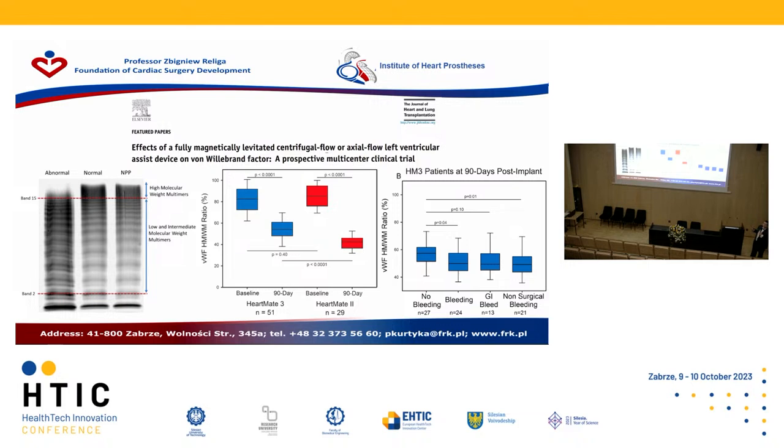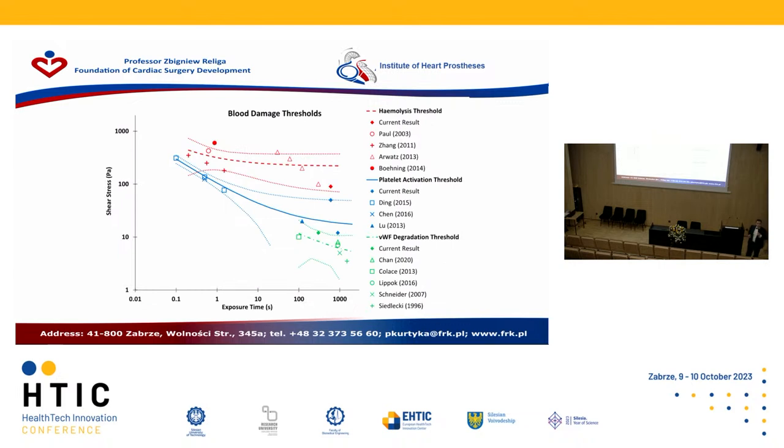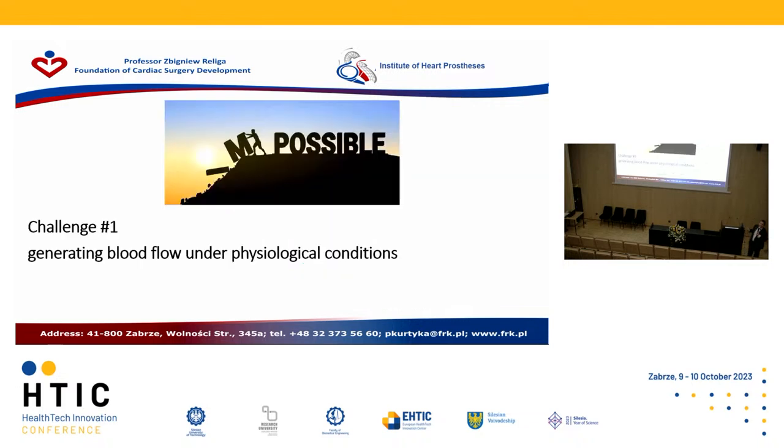Next investigation revealed that rotary blood pumps cause degradation of high molecular weight multimers of von Willebrand factor. Look at this statistic. After 90 days of support, we can observe significant degradation of von Willebrand factor, and it leads to gastrointestinal bleeding. What is the resistance of von Willebrand factor to shear? Unfortunately, it's not so high. It's about 10 pascals. So physiological blood pumping must assure shear stress less than 10 pascals.